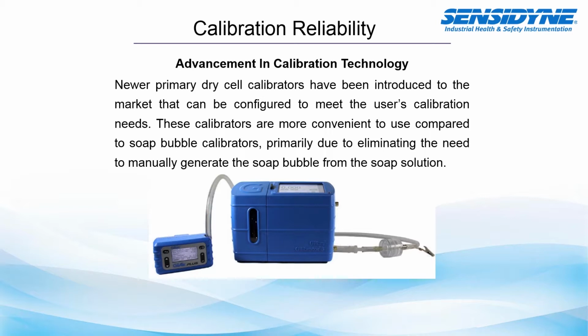So one of the larger complaints that I've heard and I've experienced in the field over the years was, while the accuracy of a bubble generator is very precise, because there's virtually no resistance of moving an air bubble through a column, and for that reason heavily relied on, having to depress a plunger over and over again to collect your sample can become monotonous and very repetitive in the field. So newer calibrators on the market, dry cells, can eliminate the need to produce individual soap bubbles.